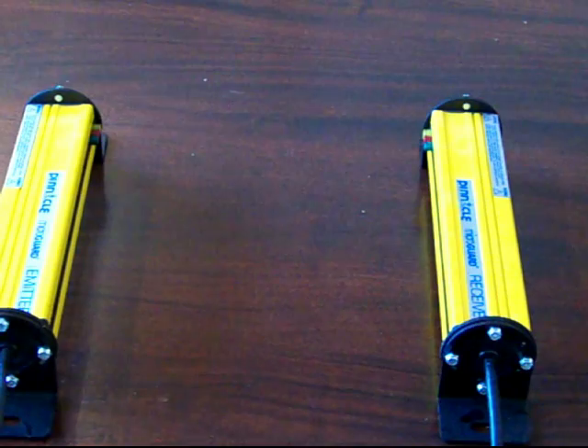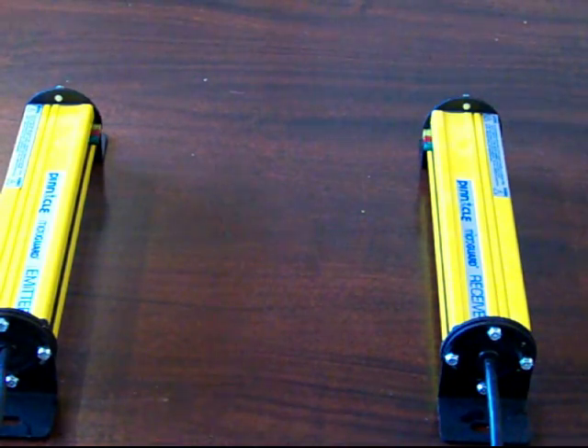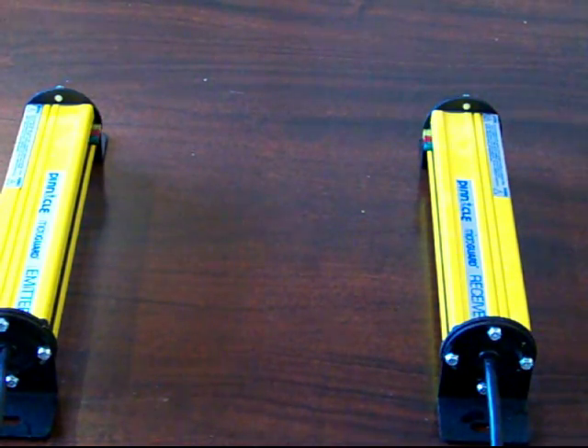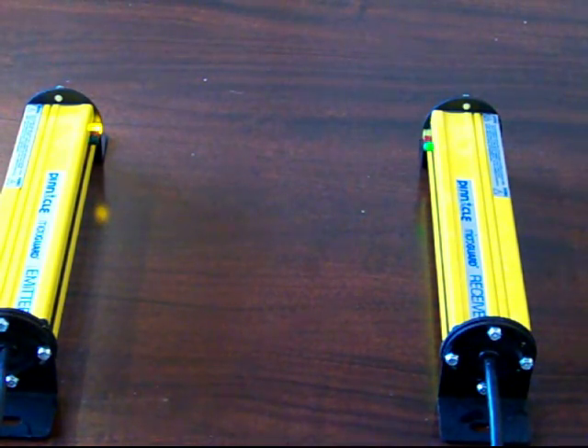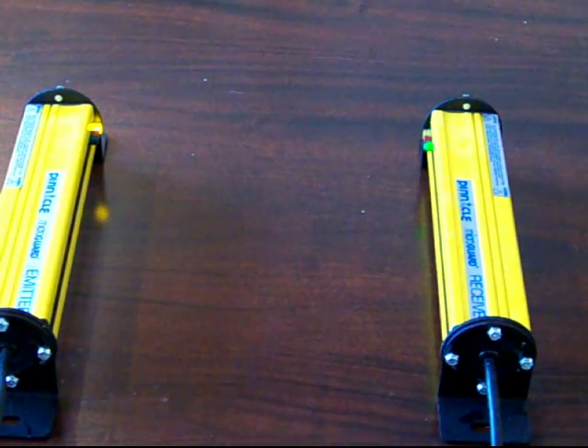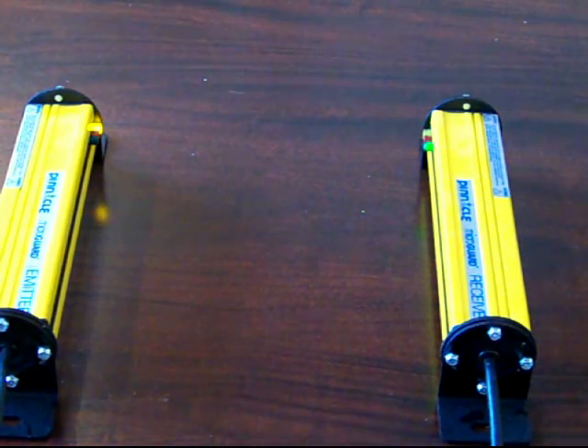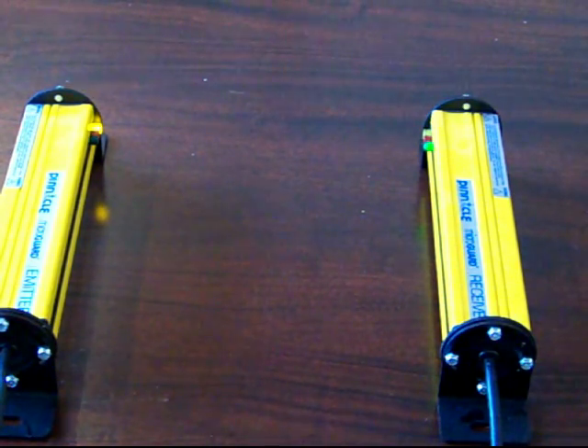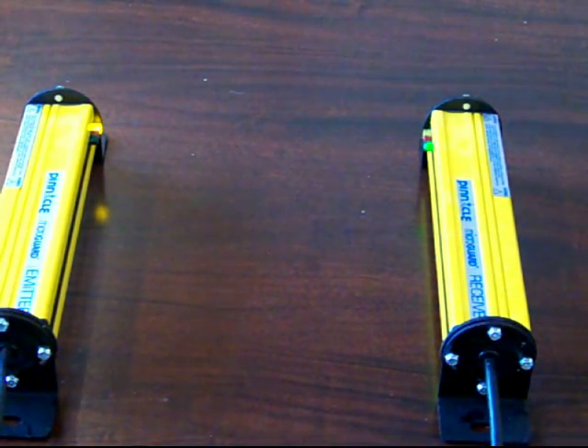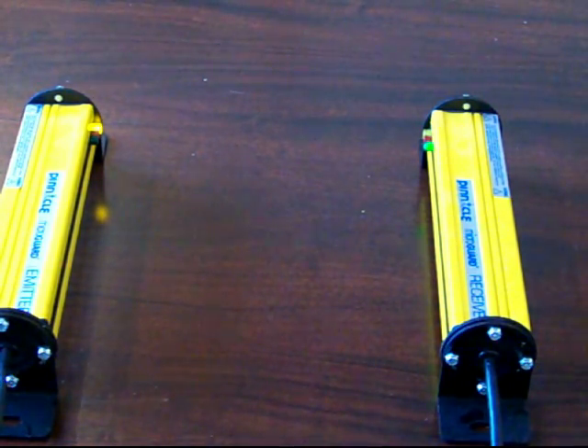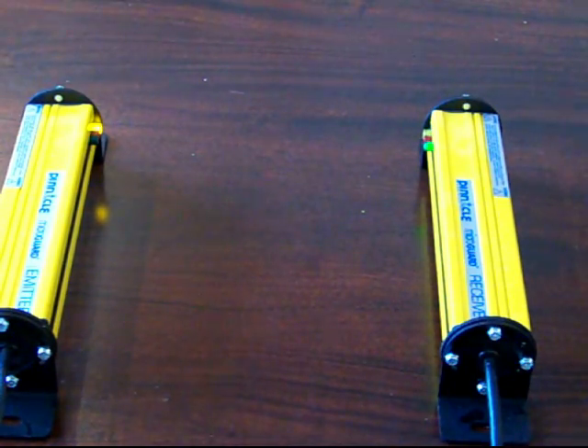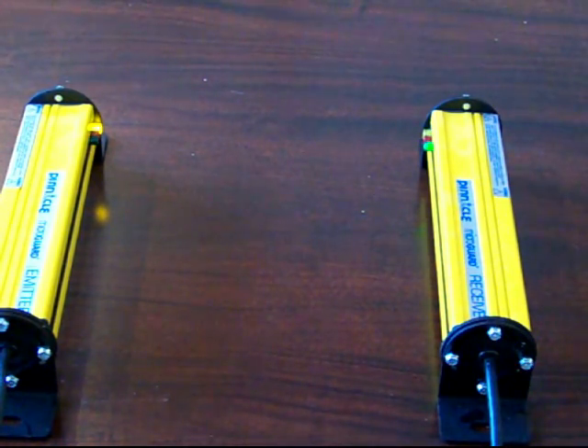You get a yellow and green flash. Then you get the two yellow and green flashes. And then instead of three green at the end, you get two green. Now you get a solid yellow on the emitter pylon with a flashing red every once in a while. And then the receiver side is actually giving you the status, whether it's blocked or not.